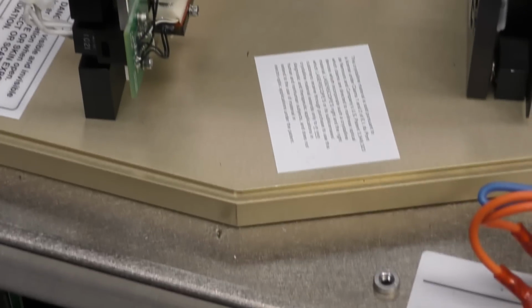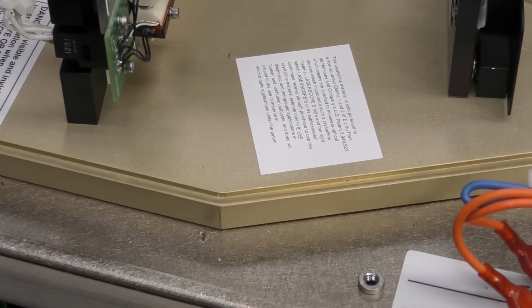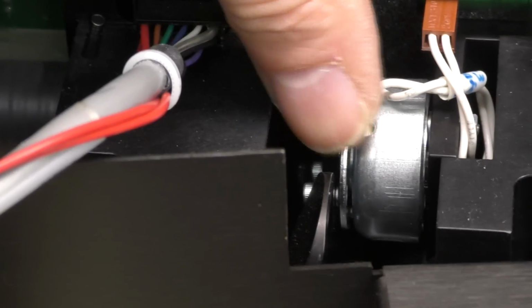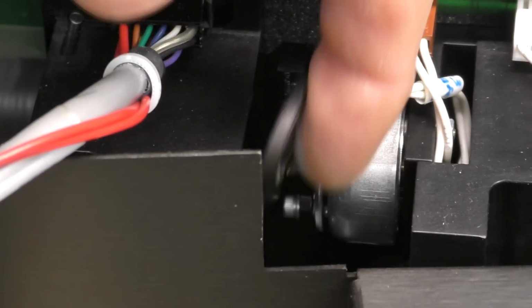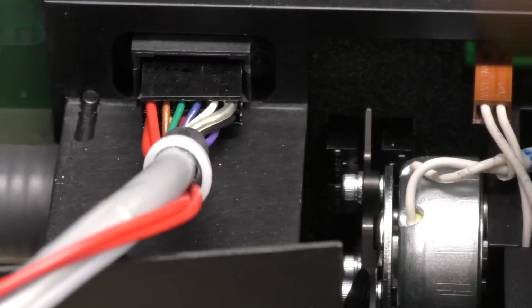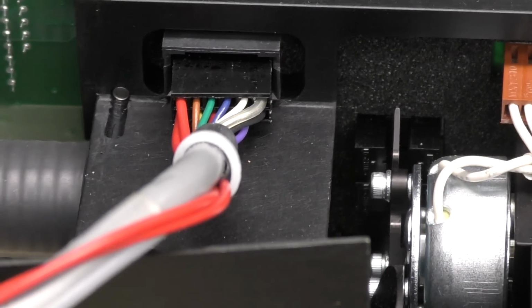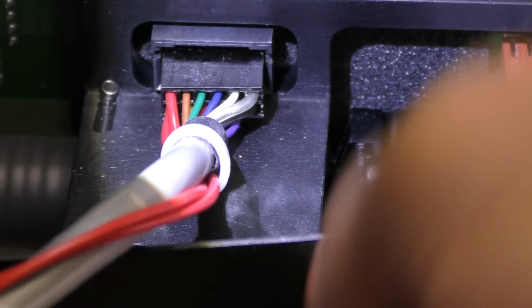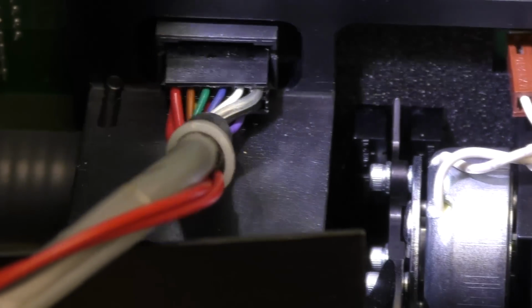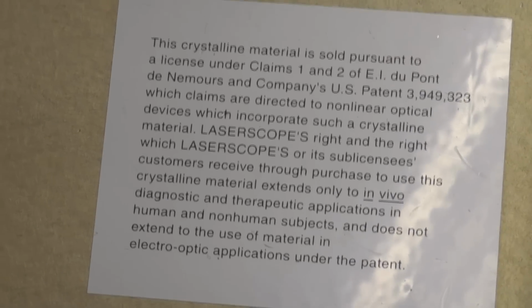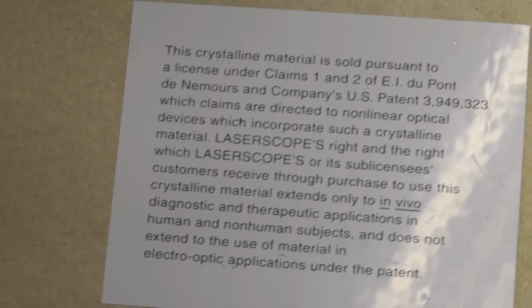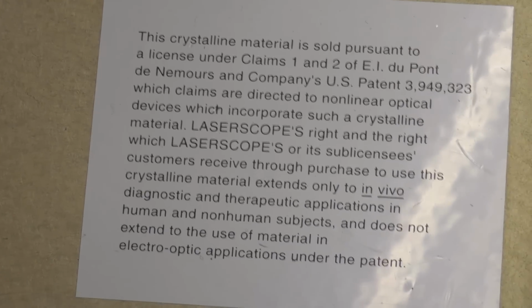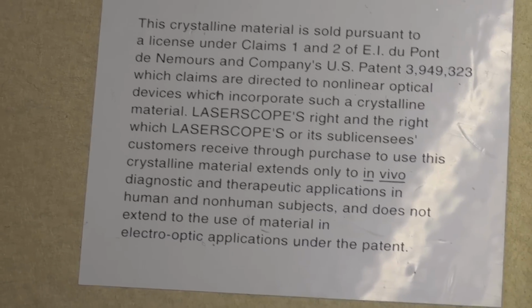And this is all mounted on this very big, sort of chunky aluminium base. That's probably about 10mm thick, so that's obviously for mechanical stability. And down here there's a solenoid operated shutter that lifts this out of the way. But just also see there's a couple of photo interrupters behind here, which are to detect the shutter position, to make sure it is actually in the position the system thinks it's in. Interesting little note here about the patents. It looks like this laser assembly is made by Laserscope, and it looks like they've licensed the use of the KTP crystal for medical use only.